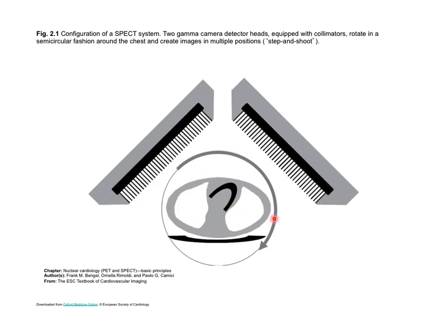So if I have the patient here, and these are those two detectors that we saw outside that guy in the scanner, we put these septa down here, and they absorb radiation. And so this detector is basically heavily weighted to looking straight down, right? So at each position here, the photons that I'm going to detect are basically in a straight line along here.